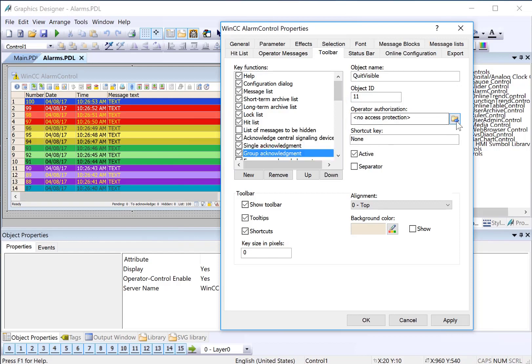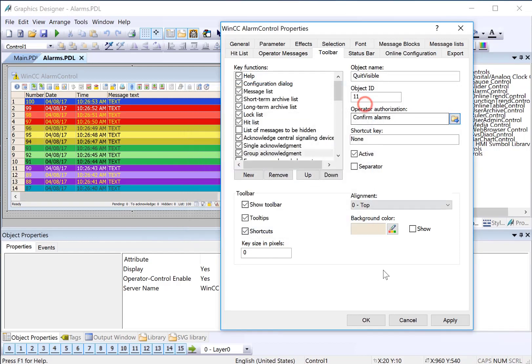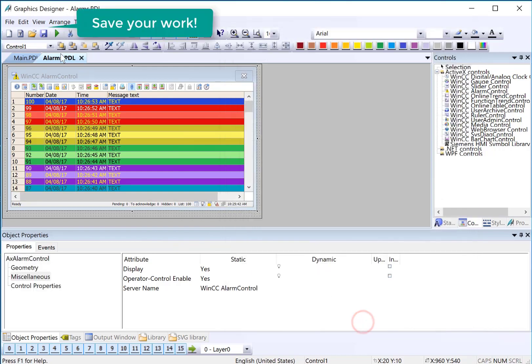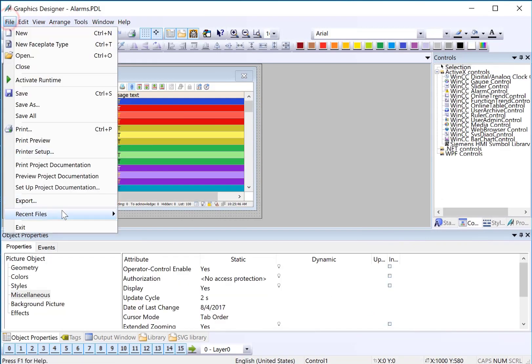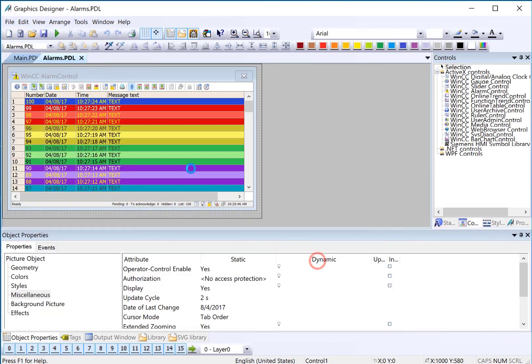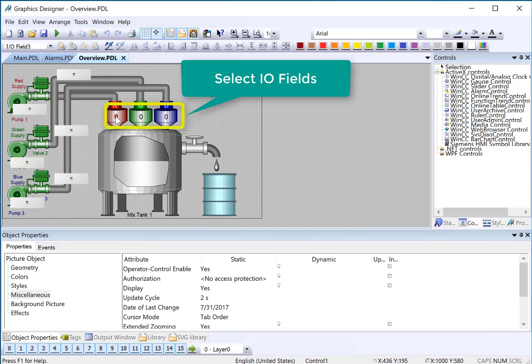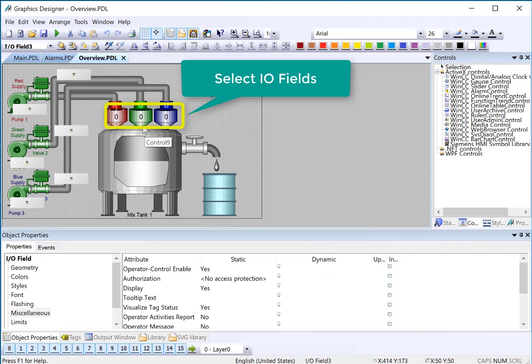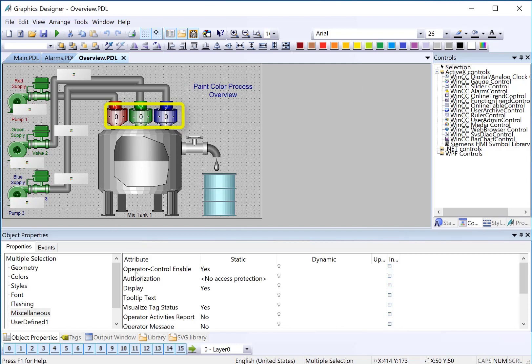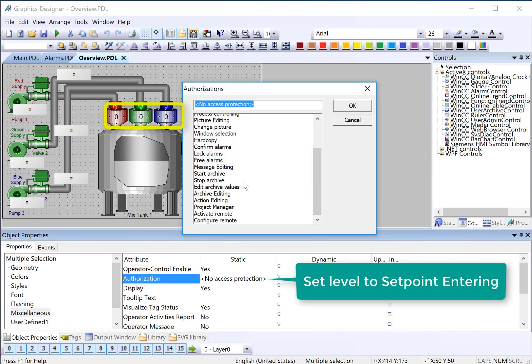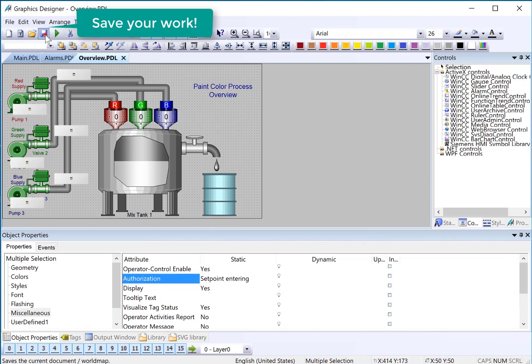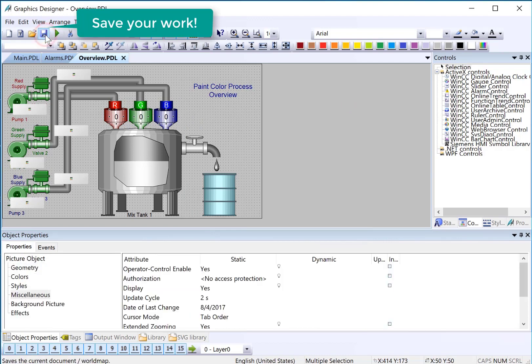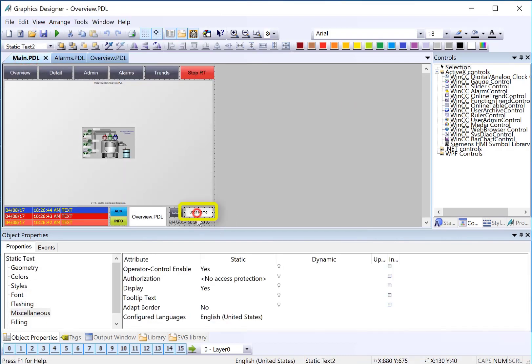Next we'll go to our overview screen and on our IO fields I'm going to select one IO field and hit Ctrl+A and it will select every IO field on the picture. That's one of my favorite features of WinCC. And on the authorization level we will use our setpoint entering which was the new one that we created and click OK and hit save.